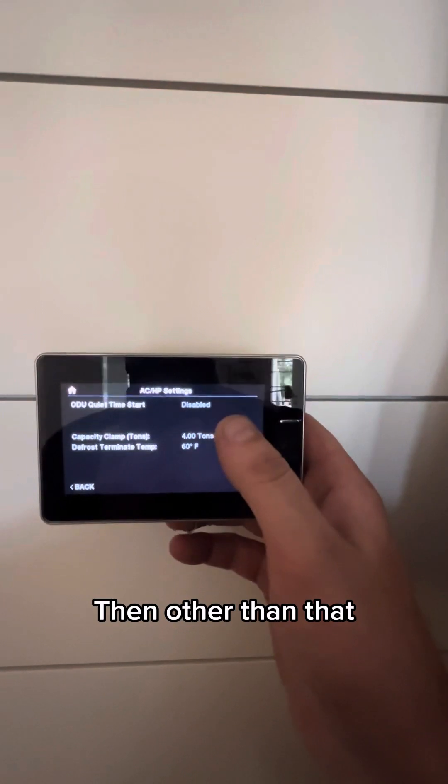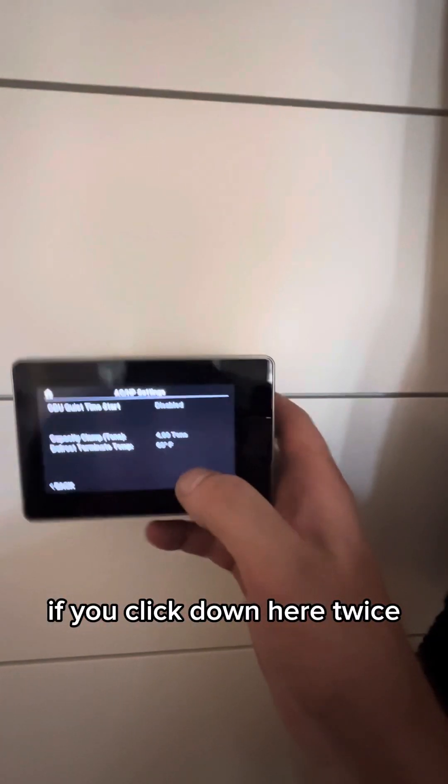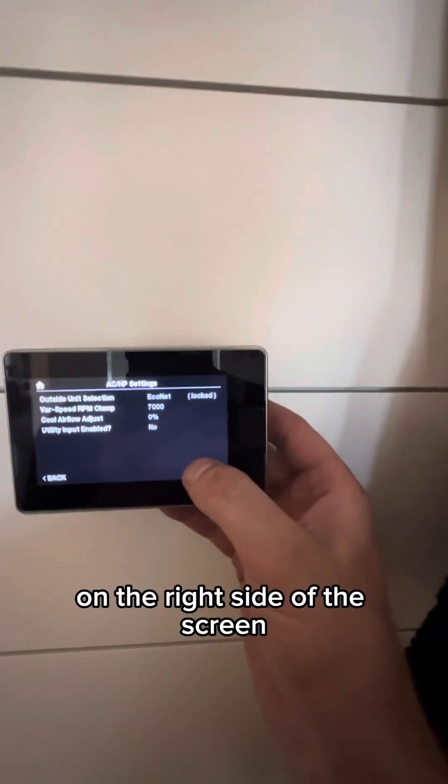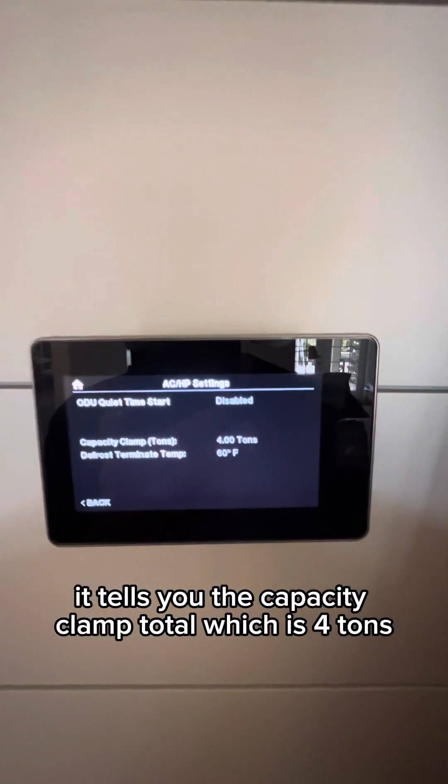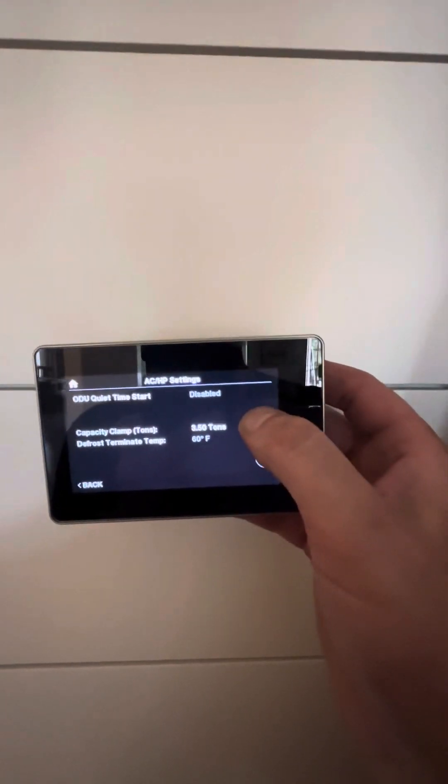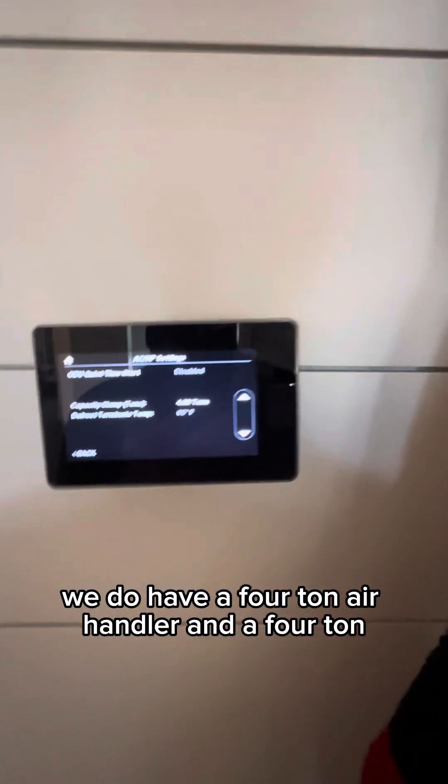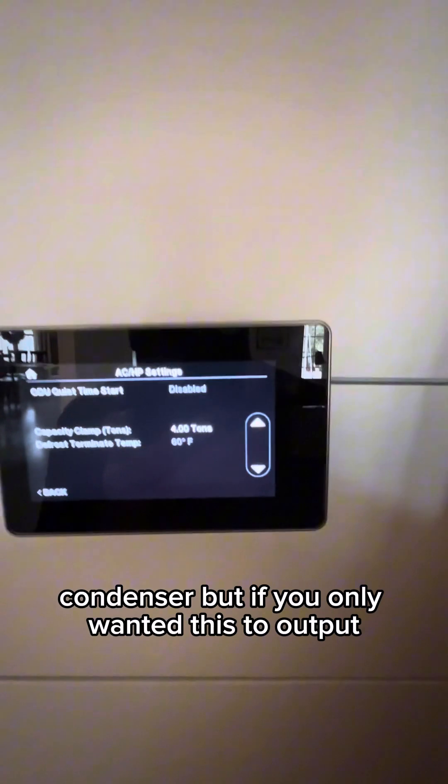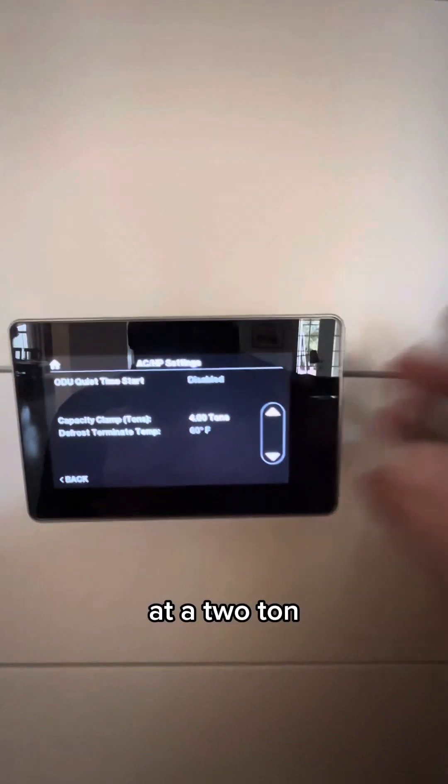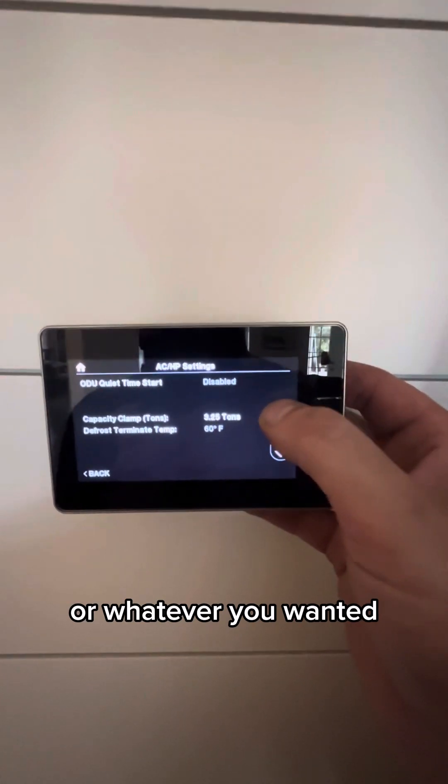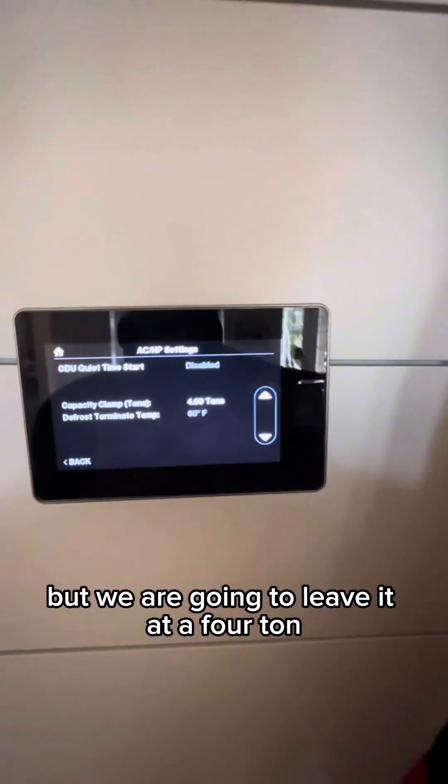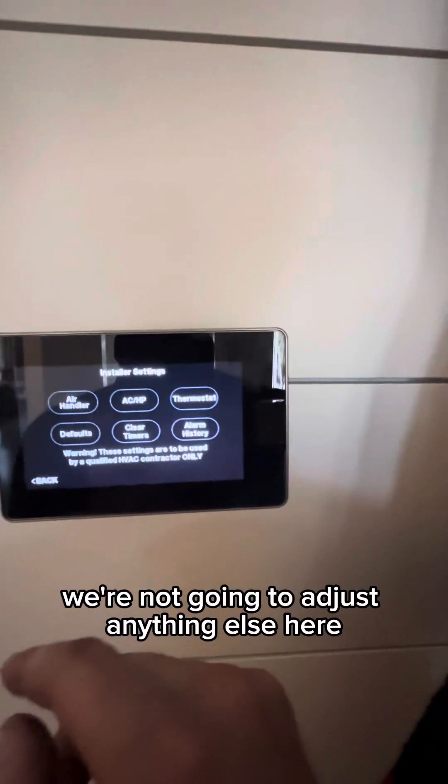And then if you click down here twice on the right side of the screen, it does take you to the next page. It tells you the capacity clamp total, which is four tons. You can actually change that. We do have a four ton air handler and a four ton condenser. But if you only wanted this to output at a two ton, you could change that down to two ton or whatever you wanted. But we are going to leave it at four ton.